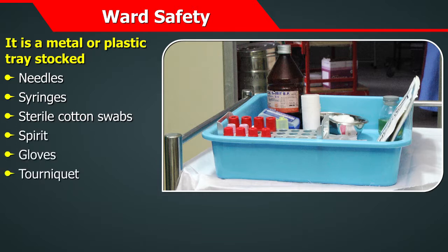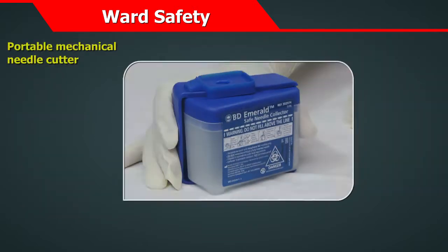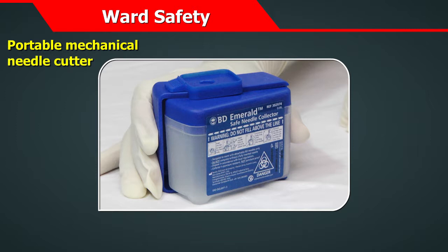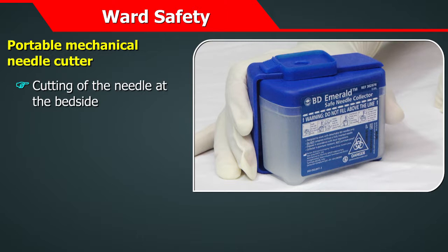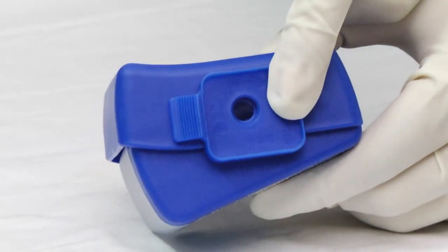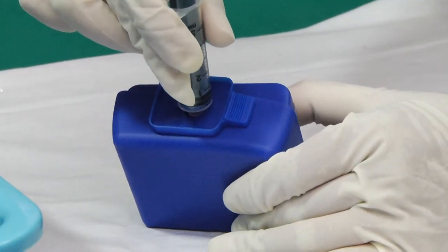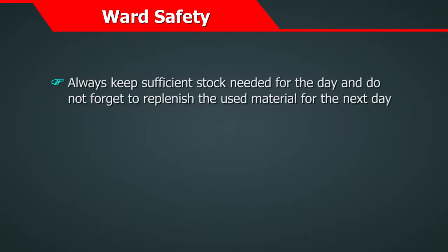An important component of the phlebotomy tray can be a portable mechanical needle cutter, which ensures cutting of the needle at the bedside and eliminates the dangerous practice of recapping or transfer of naked needles by hand. It consists of a sharp blade on the top, which can be exposed when the needle needs to be cut. The needle can be cut by pressing the two arms of the cutter together. Expose the blade, insert the needle into the hole, press the two arms together, and the needle is cut at the hub. The remaining syringe and hub can be discarded according to biomedical waste rules.